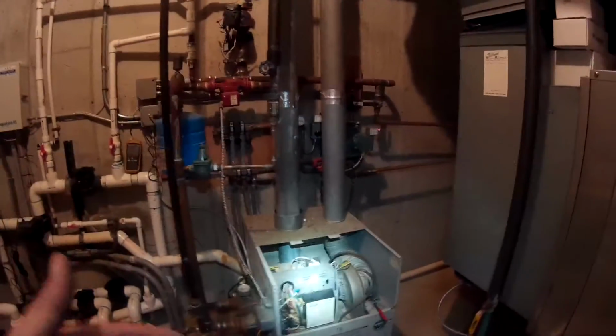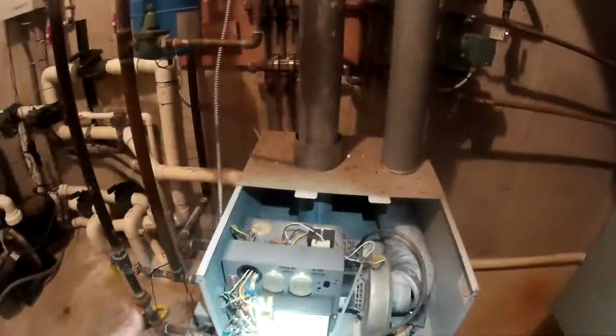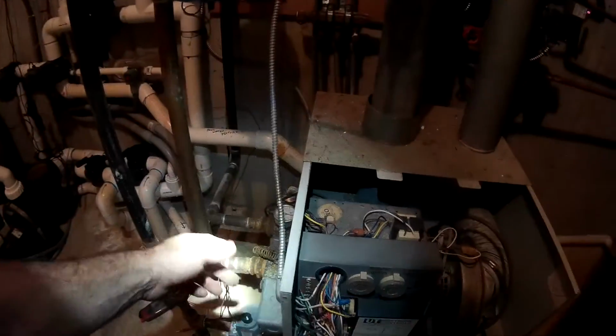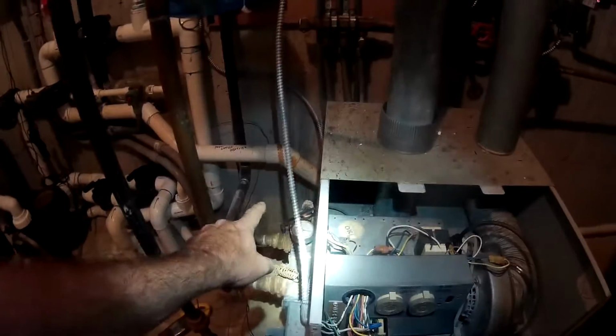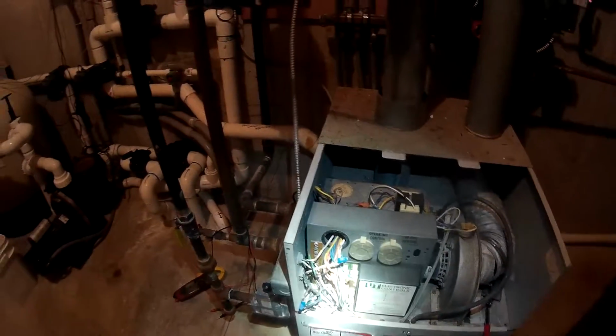And we went through all the troubleshooting, you know, just to make sure I had voltage where I needed voltage, but that high limit back there on the piping manifold was bad.